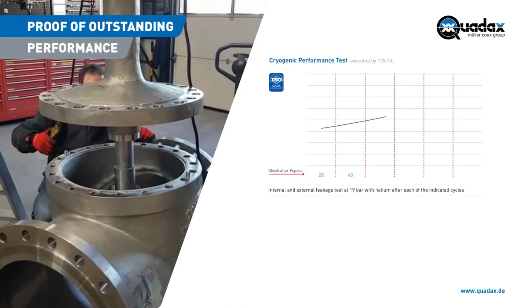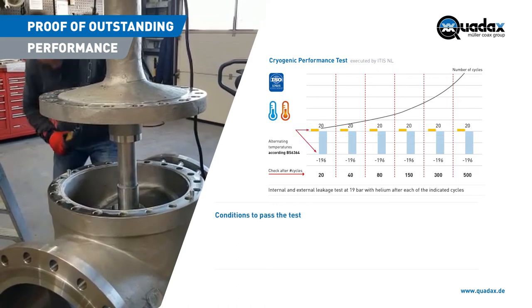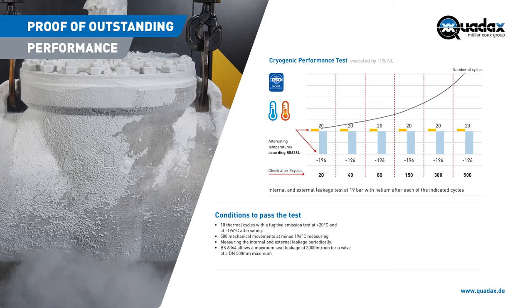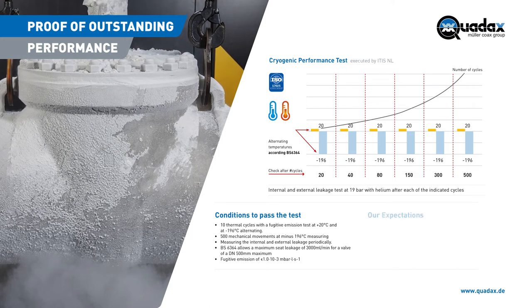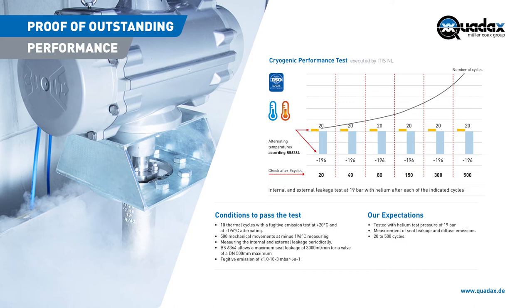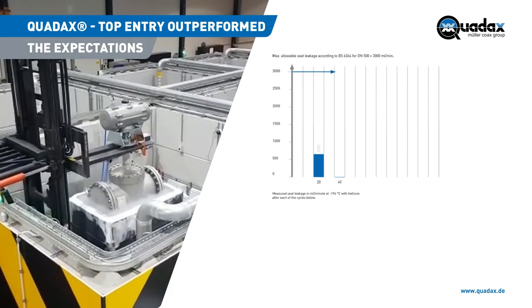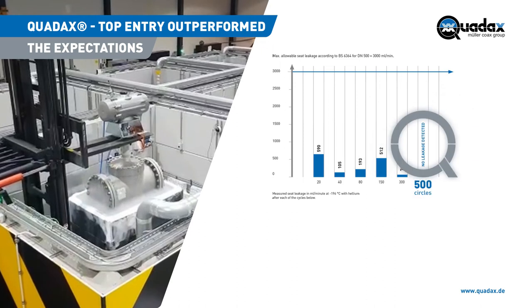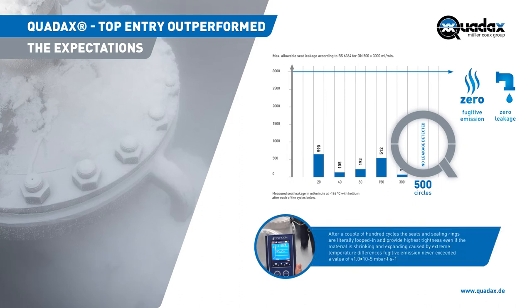Quadax outperformed in the most demanding test on the LNG market, which was based on the requirements of Europe's biggest LNG import terminal. The end-user stipulated a test with 10 thermal cycles combined with an endurance test of 500 mechanical switches. To meet this requirement, a Quadax 4-offset butterfly valve with specifications DN500 mm and Class 150 was tested at the ITIS Test Laboratory in the Netherlands. The test institute ITIS-BV certified that the seat leakage never exceeded the low value of 990 millilitres per minute, and after 500 cycles, zero leakage at all was detected. The fugitive emissions were well below the norm and hardly measurable.